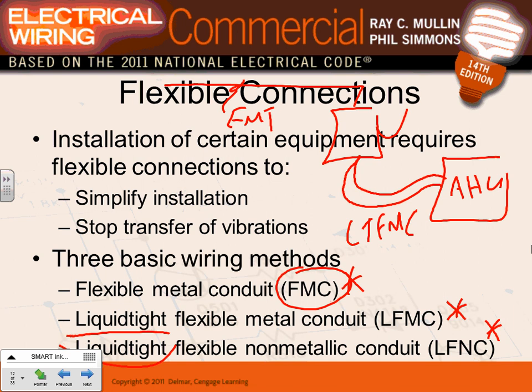Very important: when using flexible metallic conduit to tie to equipment, you have to pull an equipment ground conductor inside the flex. The flexible metallic conduit itself is not qualified as an equipment ground conductor. There's an exception for lighting fixtures - six feet or less at 20A - but for mechanical equipment, always pull an equipment ground conductor.